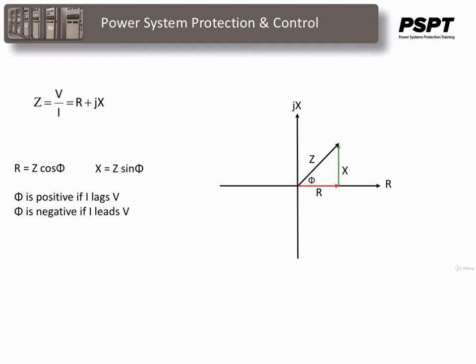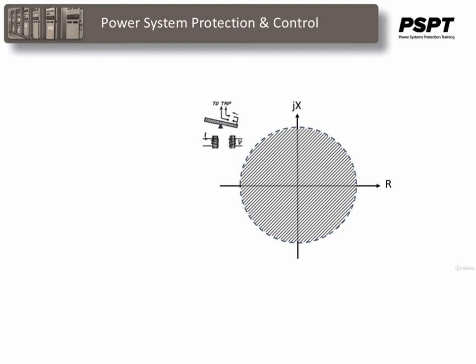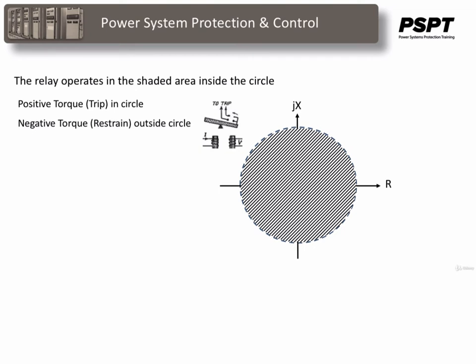Relays which measure plane impedance Z are called impedance relays. The characteristic on an R-X plane is a circle with the center at the origin and a radius equal to Z. Relays which measure impedance but respond to faults in one direction only are called directional impedance relays. The basic impedance relay characteristic circle is not directional — it will operate for any impedance inside the circle. The impedance relay operating characteristic is a circle on an R-X diagram, and it will pick up for any combination of V over I that falls inside the shaded area.